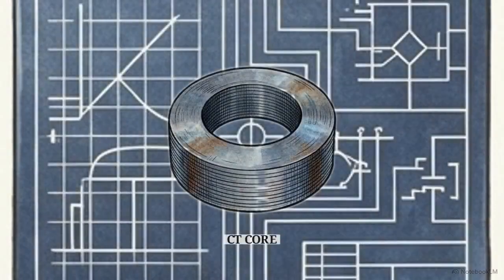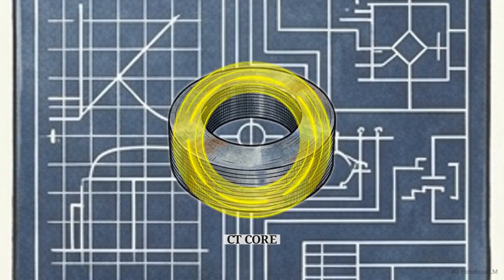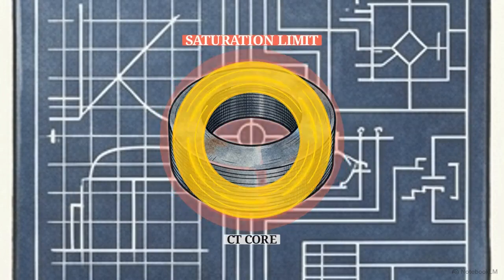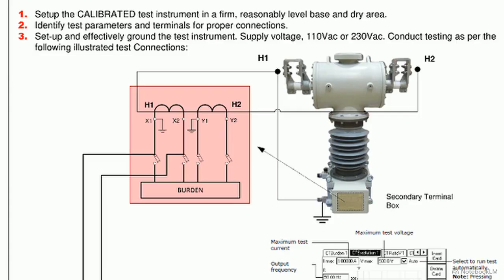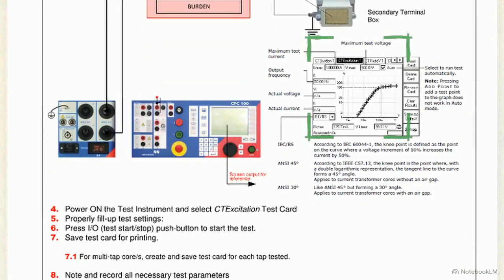The goal is to map the magnetic saturation limits of the CT core to confirm it is suitable for its designated protection class. This test is run in reverse. The CPC100 operates by driving an AC voltage into the secondary circuit at X1 and X2, while recording the exciting current, keeping the primary circuit completely open. This screen output graph displays the resulting excitation curve.